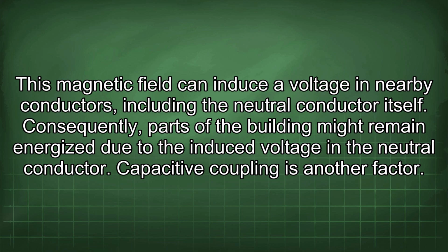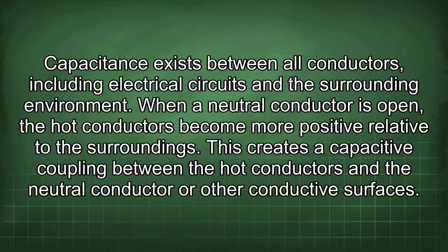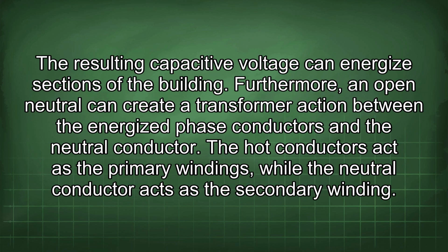Capacitive coupling is another factor. Capacitance exists between all conductors, including electrical circuits and the surrounding environment. When a neutral conductor is open, the hot conductors become more positive relative to the surroundings. This creates a capacitive coupling between the hot conductors and the neutral conductor or other conductive surfaces. The resulting capacitive voltage can energize sections of the building.